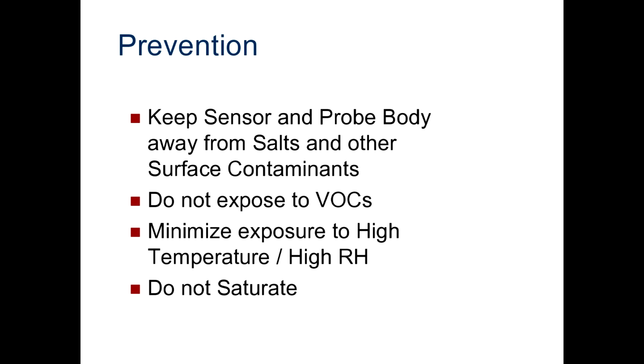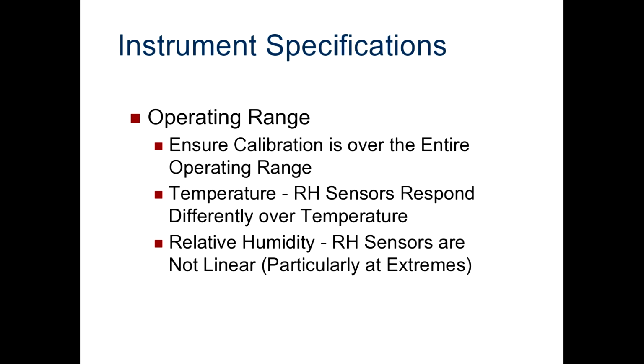And don't allow saturation or condensation to occur on the probe body or the sensor, particularly at high humidity levels, as that can also cause hysteresis or in some cases non-reversible drift. It's important to look at instrument specifications as well. Ensure that the calibration is over the entire range that the unit will operate.